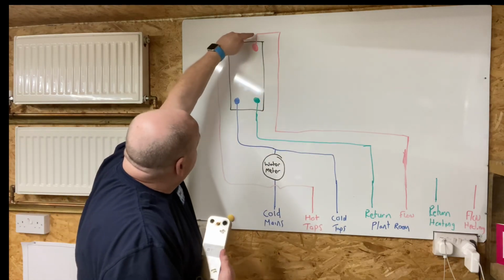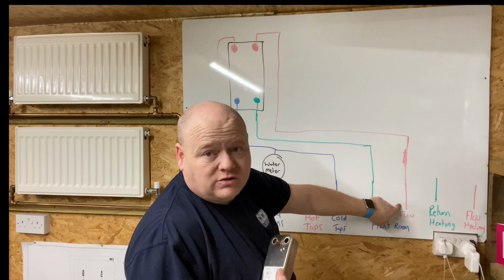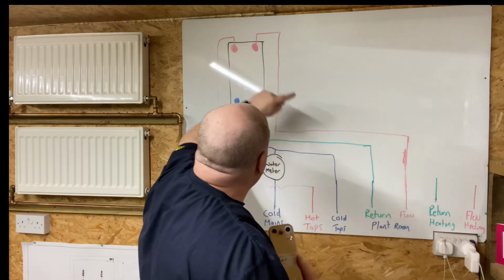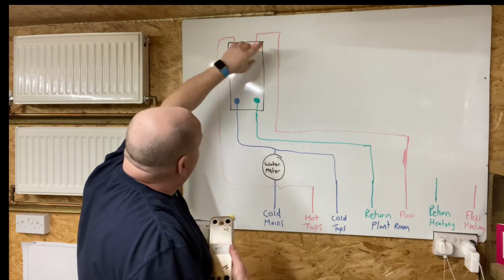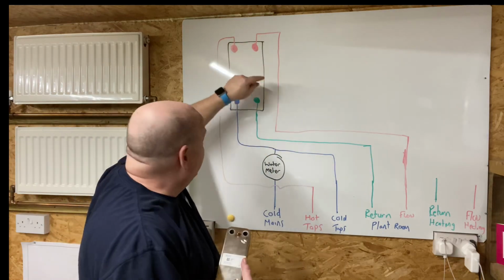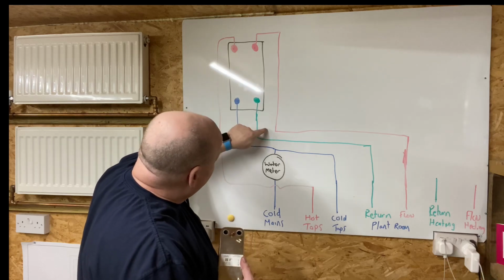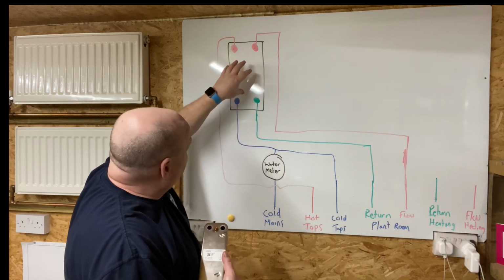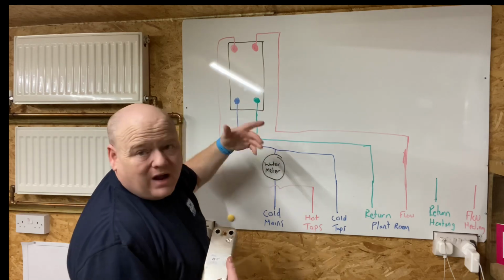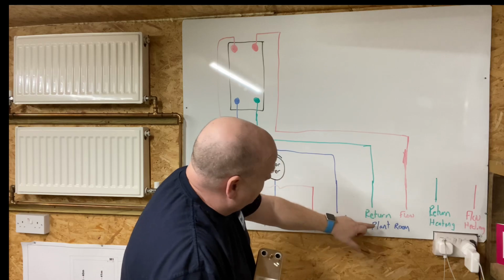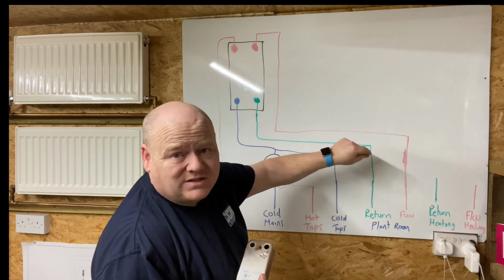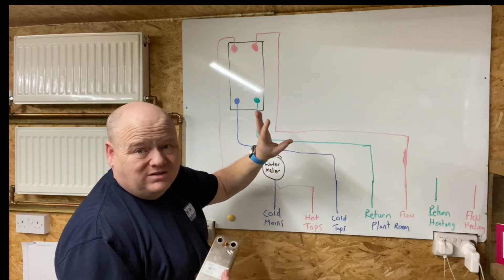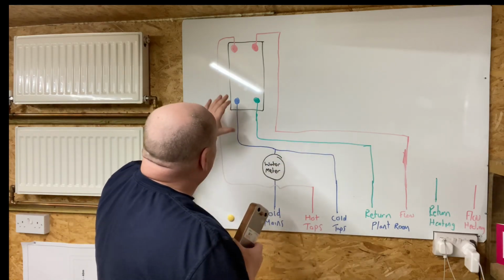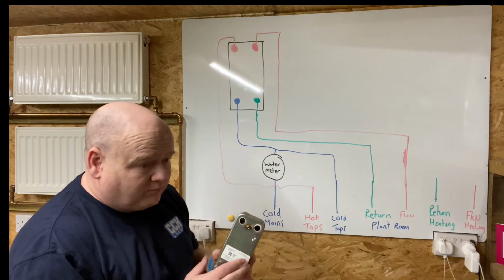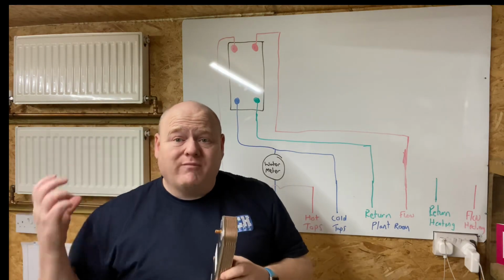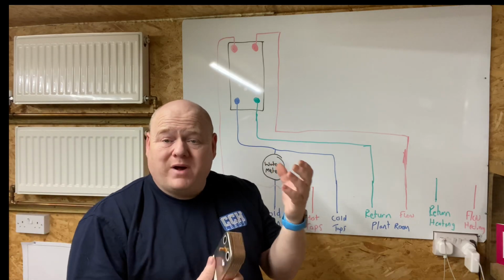This side of it, this is your main flow, so that's coming from your plant room, and there's going to be valves and stuff on here, but I'm just trying to simplify it so you can understand what's happening. And then that's going through the plate, and once that's cooled down a little bit there, it's took the heat out of it and gone to your hot tap, or took part of the heat out of it. Again, that's going to go back to your plant room, and again there's going to be some more T's on this shortly, but I'm just trying to do it so you can understand it a little bit better. So what that plate is doing, it's transferring the heat from the plant room into the water that's going to come out of your hot tap.